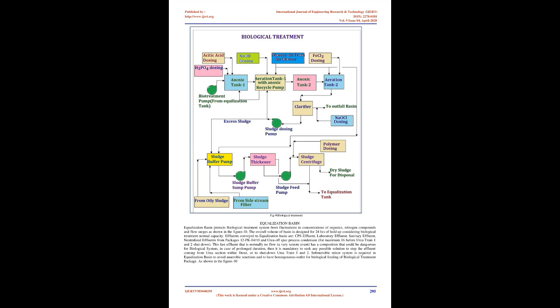Clarifier. One clarifier constructed of RCC epoxy material, with a size of 12.8 mDia x 3.5 mH, is provided. After the nitrification, denitrification and aeration process, the mixed liquor flows to the clarifier, where the activated biomass is separated from the liquid during a period of quiescent settlement. The settled biomass, called sludge, is pumped back to the anoxic tank to maintain the biological population. Precipitated phosphorus is also removed by settling.